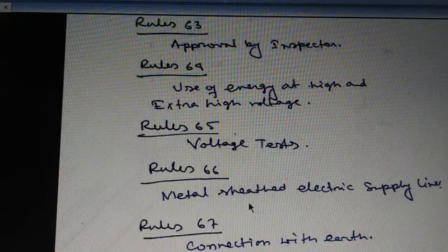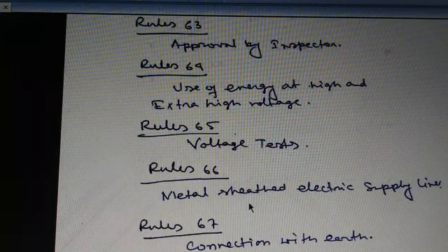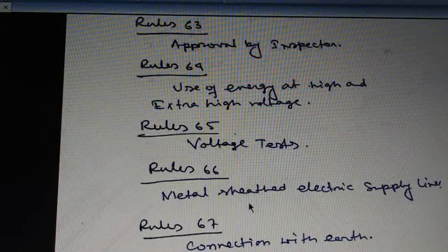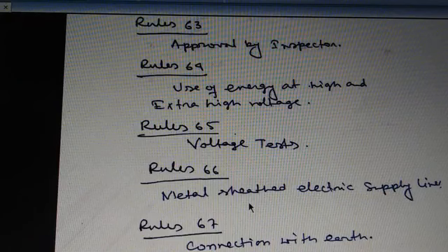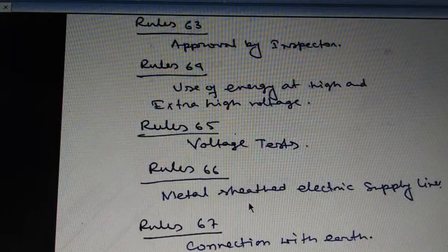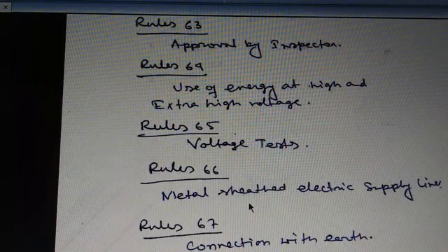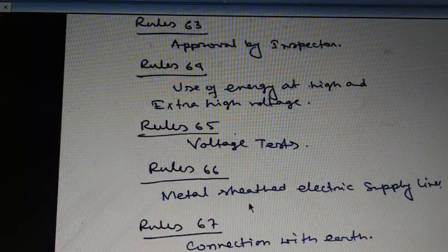Next, in the event of failure of insulation occurring between the conductor and the metal sheathing at any point along the electrical supply lines as connected, the impedance of the relevant circuit shall be such that the current resulting from such failure shall not be less than twice the value of the current for which the suitable cutout is installed in the system.